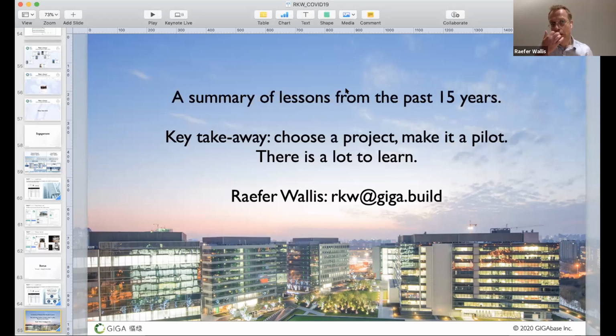We've seen buildings that apply for reset follow this process: they start with monitoring and discover that the filtration, of course, has to be different top to bottom, and specify different levels of filtration at different heights, which reduces energy consumption and increases overall performance. You can't figure any of that out without the data.